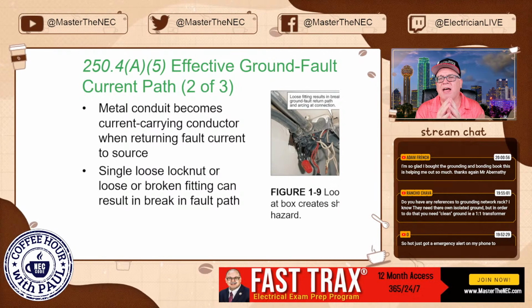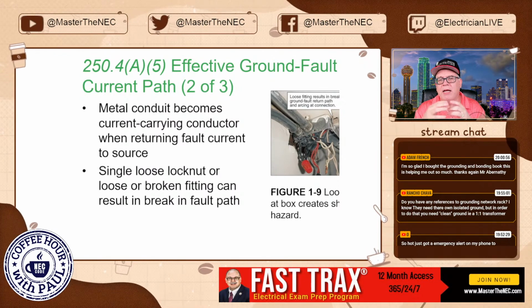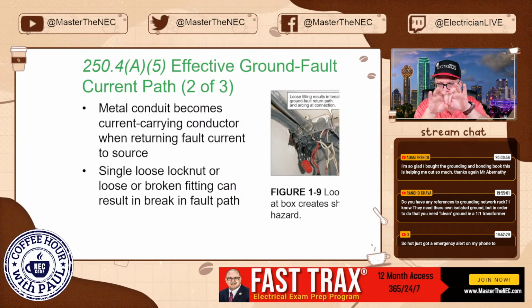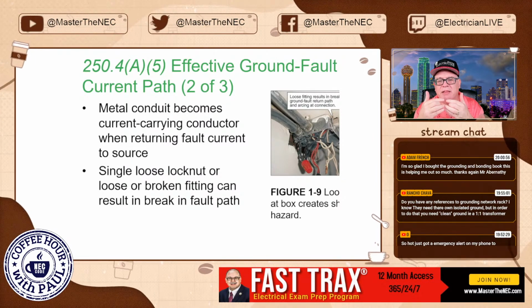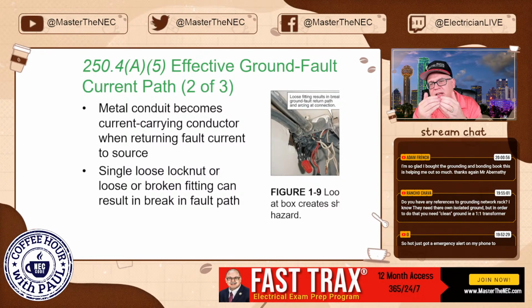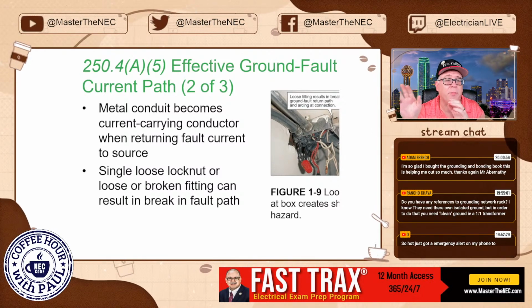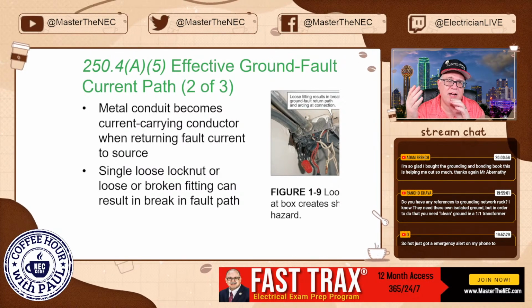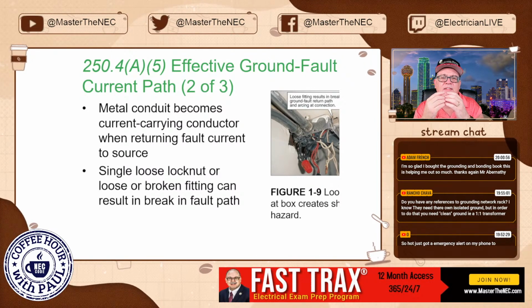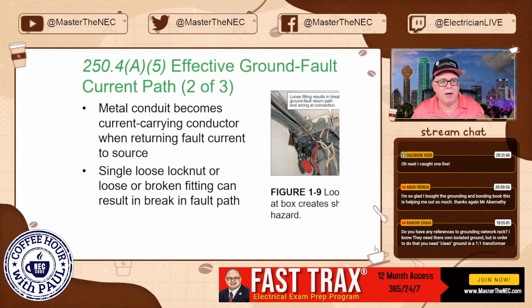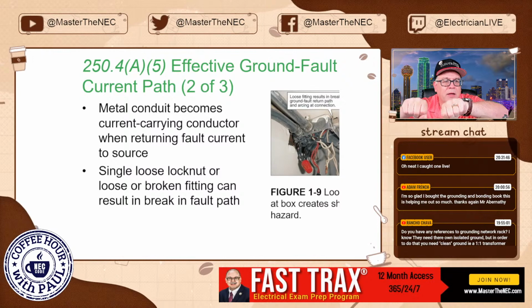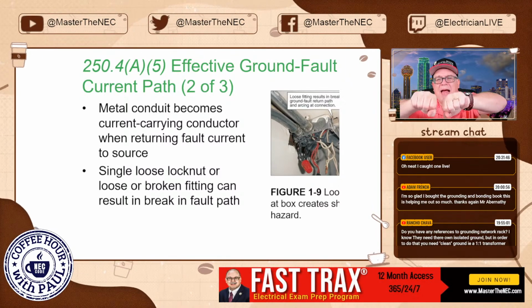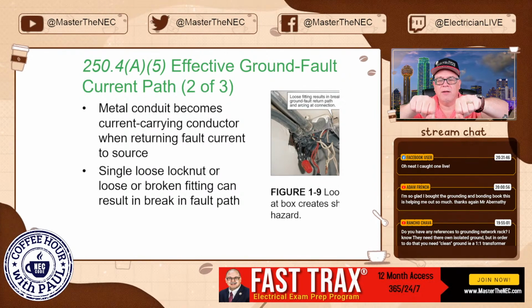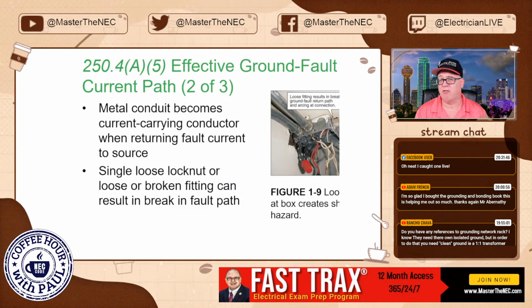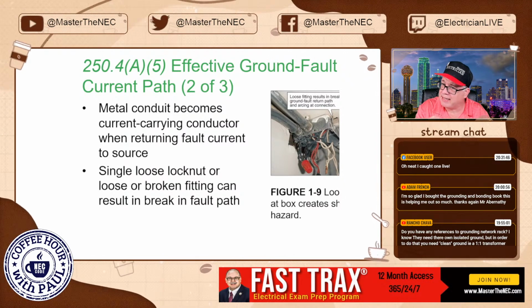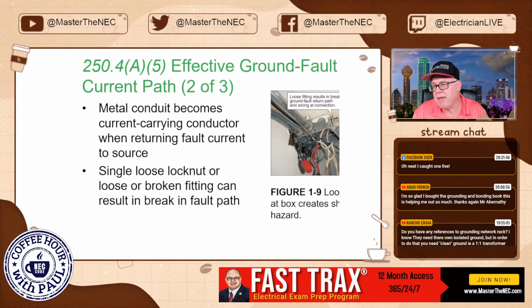Can you imagine if you have a fault on a raceway and you have a loose coupling, and you know they fit loosely, they're not all together tight, or it pulls apart just enough. And now they energize this raceway, but it doesn't clear the breaker because they didn't run an equipment ground in there. They're using the raceway. And it sits there until you come up, right? And you grab it and you put them together. Or you grab it and now you've got current across your heart. Just for that brief moment, that might be all it takes. Why? Because somebody did not put the fitting on properly. Or maybe it worked loose.